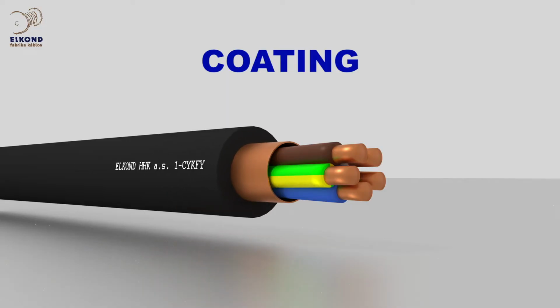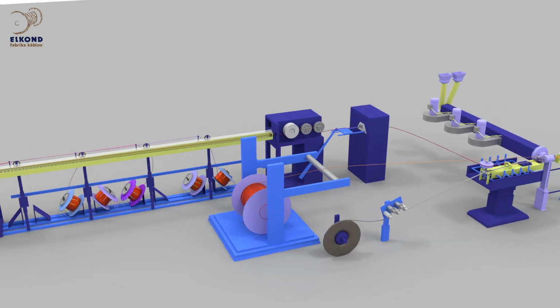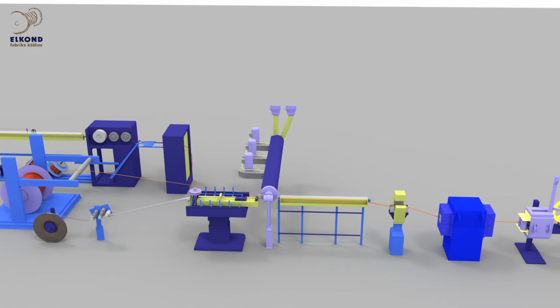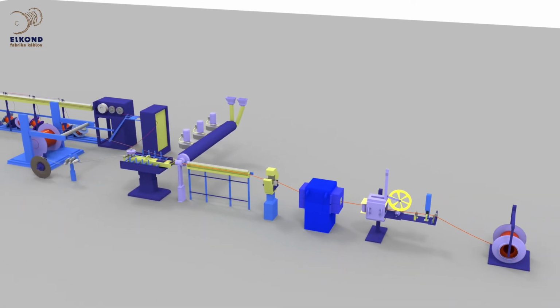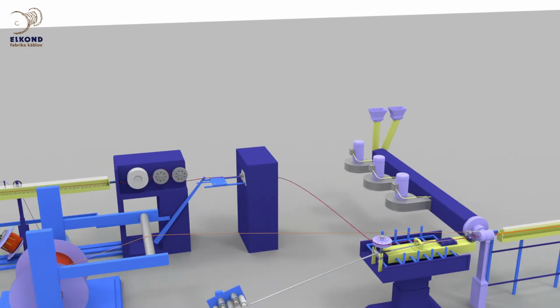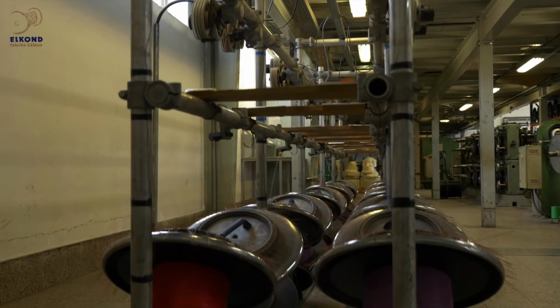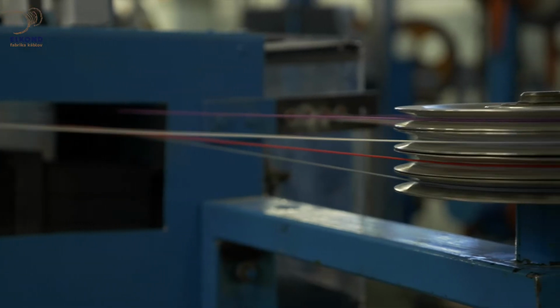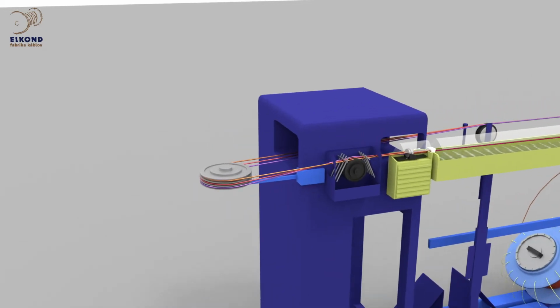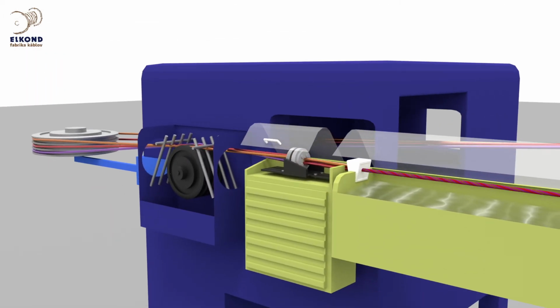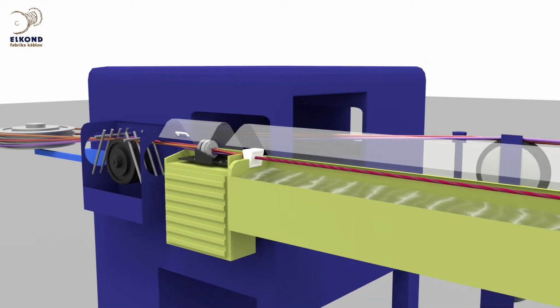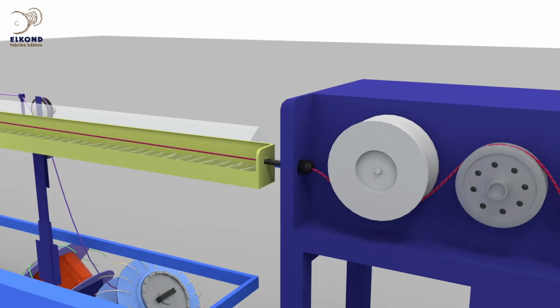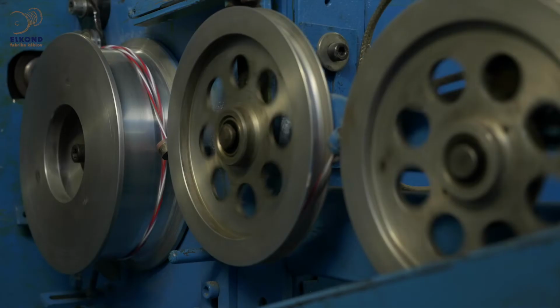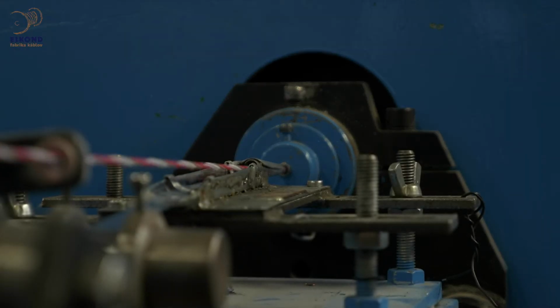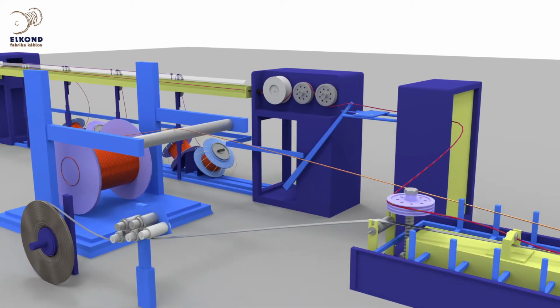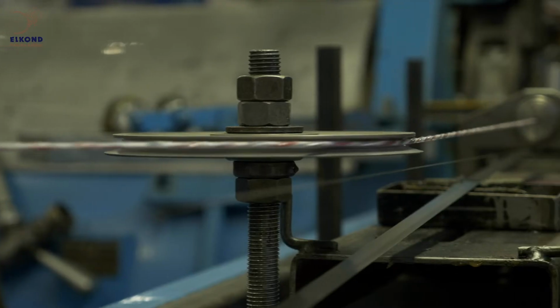Prepared cable cores go to the final phase, coating. The principle is similar to the insulating process and done on specialized coating lines. Optimization of this production process is very important in terms of costs. An undisputable advantage is that for production of some cable types, we use coating lines that include also a stranding machine. One line does stranding of insulated wires, screening by a tape, and applies final protective coating.